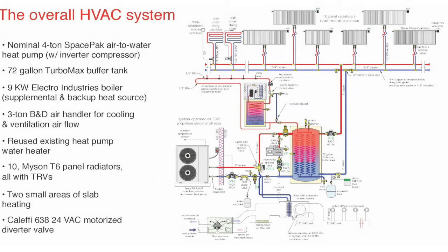We watch this pump operate. Typically, it's between 20 and 30 watts. So you're delivering all the heat you need to this house using 20 to 30 watts of electrical input. And again, remember, we talked this morning about distribution efficiency. You could probably pull your phone out and do the numbers, 35,000 divided by, say, 25 watts. It's pretty good on distribution efficiency.